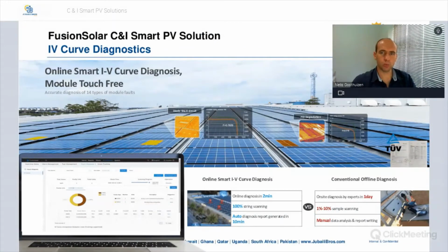A great feature of the Huawei inverters is the IV curve diagnostics. It's the smart IV curve diagnosis, which allows you to identify up to 14 faults accurately without having to be on site. It's a system designed online, so it's online smart IV curve diagnostics. A system can be diagnosed in as little as 2 minutes. 100% of the strings are scanned, and an auto-diagnostic report is generated in about 10 minutes. If you compare the online smart IV curve versus the conventional offline diagnosis, you're looking at 2 minutes versus 1 day if you need to send somebody out to site to do the physical inspection.